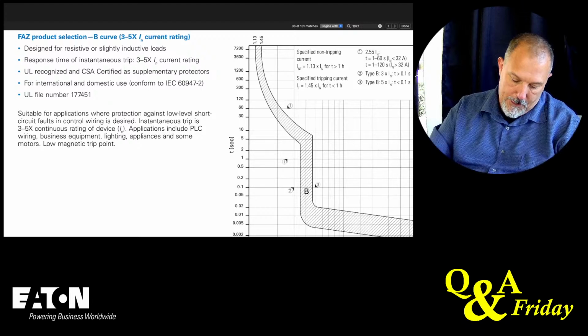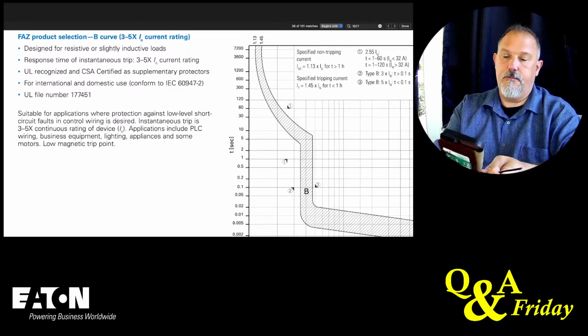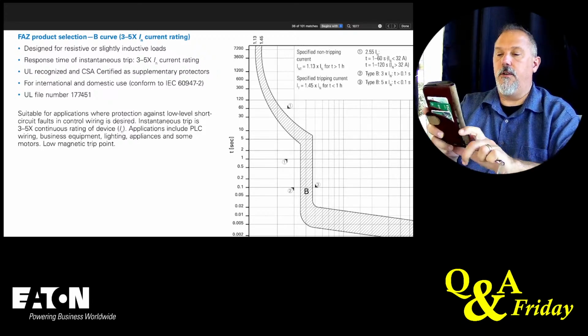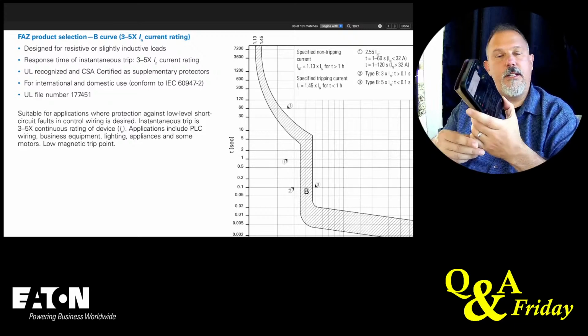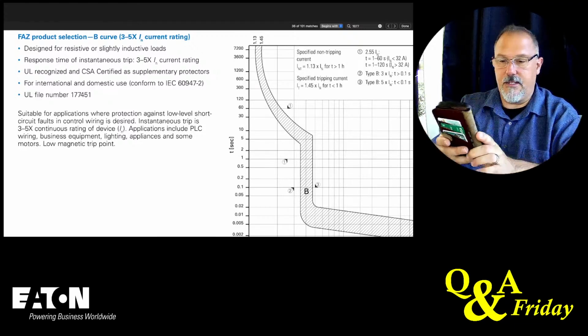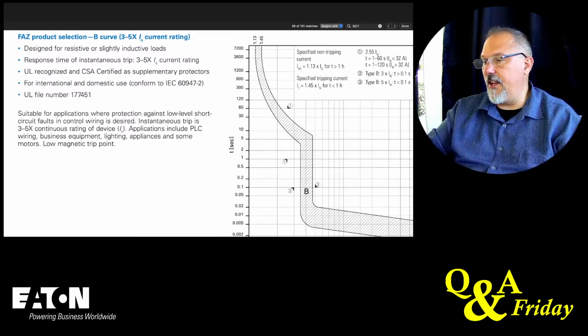All right. Oh boy, I got comments coming in. Hold on. I'll get my glasses. IEEE standard 1584 for arc flash states that only the upstream protective device can be counted to provide arc flash protection if there's no barrier between the line side and load side. This is because a fault on the load side could jump to the line side.